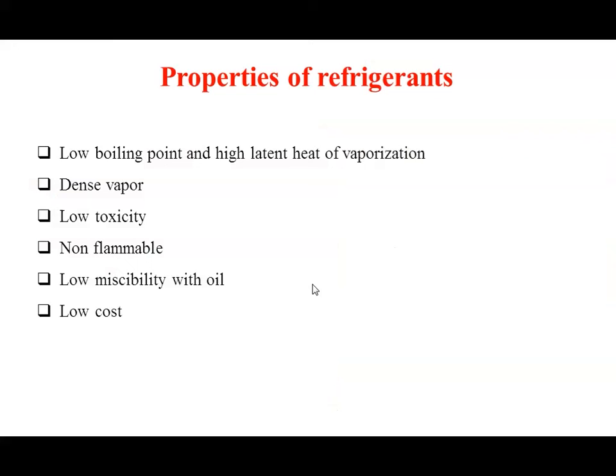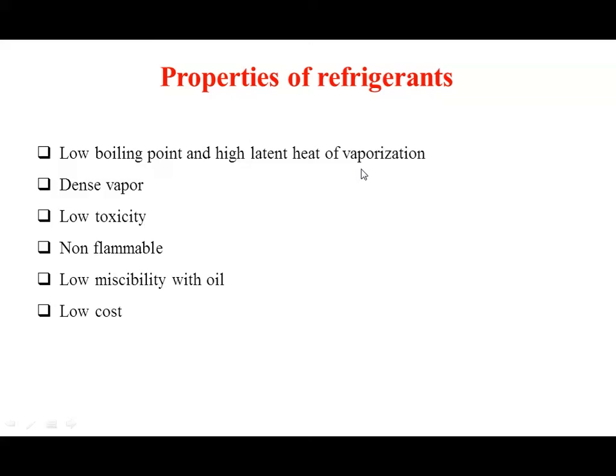The working substance used in refrigeration is called the refrigerant, and its properties play a very vital role in the refrigeration process. These special substances have special properties such as: low boiling point, high latent heat of vaporization, high vapor density, low toxicity, non-inflammable, low miscibility with oil, and low cost. The low boiling point is very important — these refrigerants start boiling at room temperature. A high latent heat of vaporization means the refrigerant is more effective.